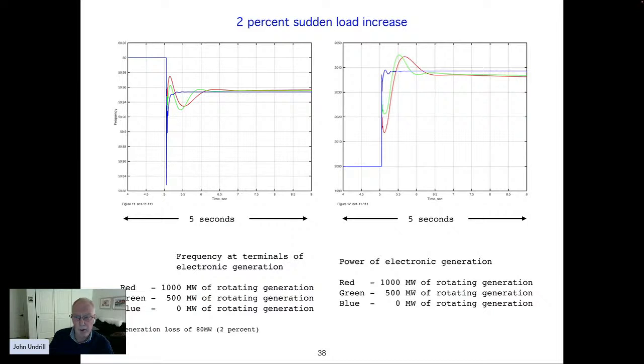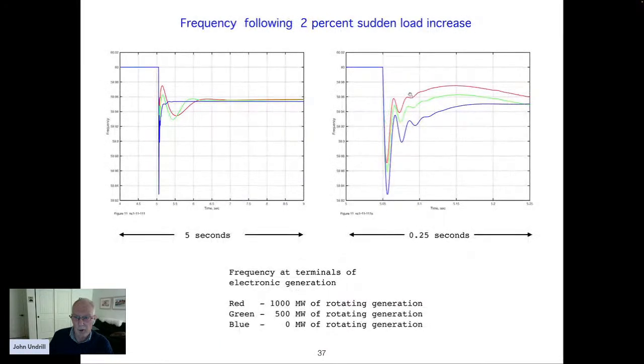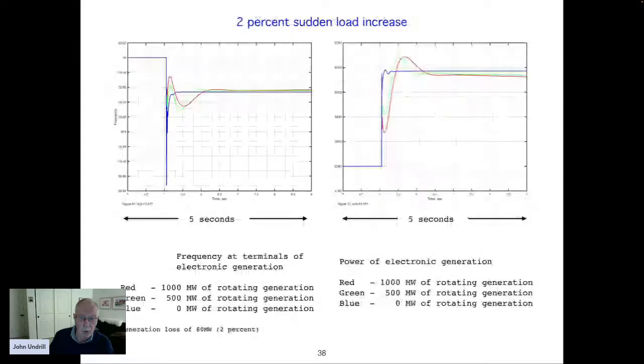So it's either LED lights or it's inverter-driven air conditioners on the sides of apartment buildings in Singapore, or it's the electronic drives of a large steel mill somewhere in Brazil. But everything's electronic. There is no direct connect of synchronous machine devices to the electric network. And yet the behavior still has the same basic characteristic of a dip to a frequency nadir, a recovery about halfway back, and then secondary control to take care of the realignment of everything over the ensuing minutes.